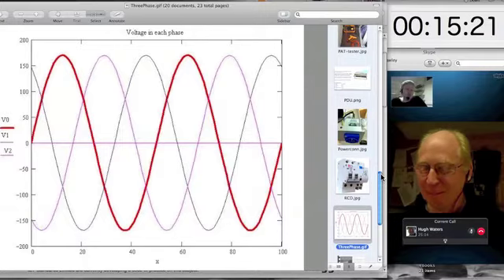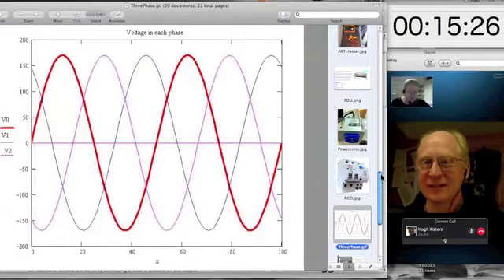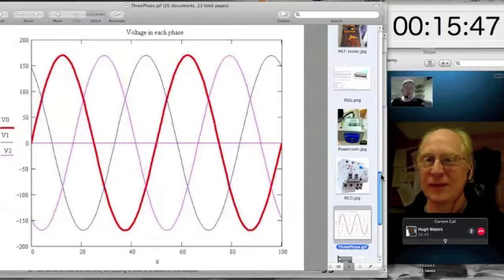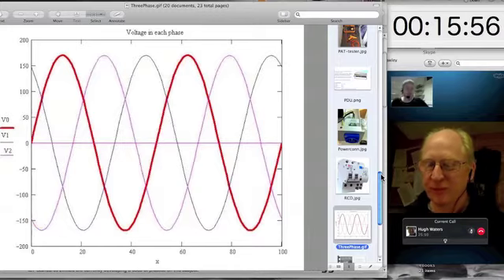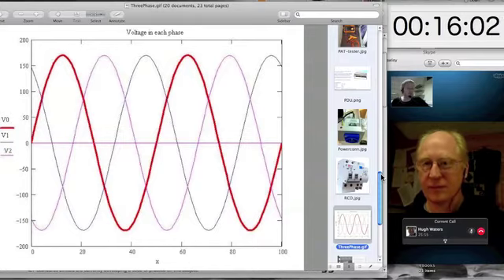That huge, great generating plant, at the coast in Essex or wherever it's coming from, burning lots of fossil fuel to heat water, to turn a turbine, to make electricity. It just turns out that the most efficient way of converting that motive force of the spinning generator into voltage is not to have a single coil wound around the spinning magnets, but to have three coils and to be picking up that induced electrical current in three phases rather than in a single phase. And so as the power leaves the power station where it's generated, it's travelling out on three live cables and a single neutral return cable.